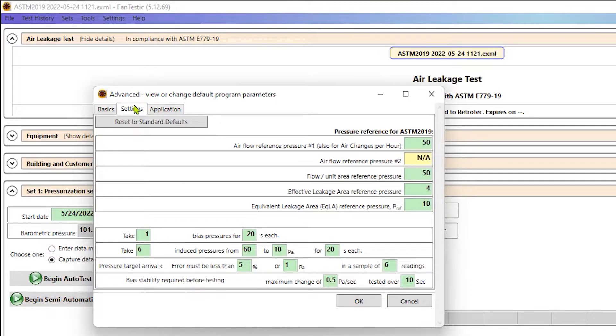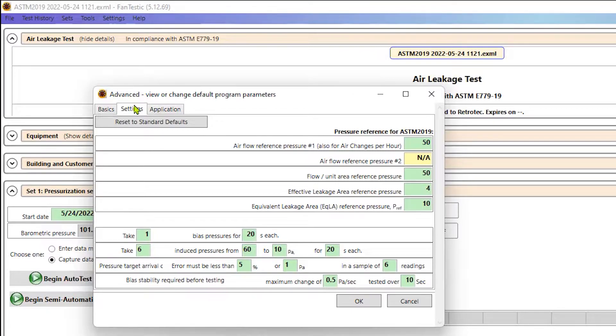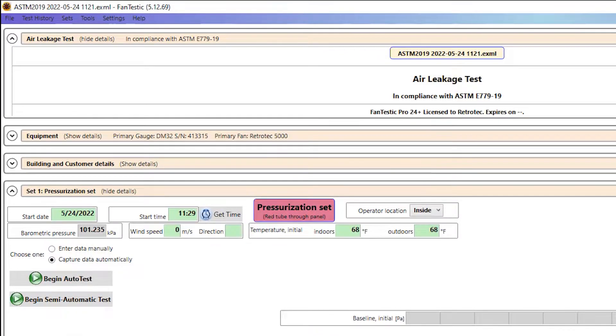And then under the settings tab, this is where we put in our reference pressure. So today, we're going to do a residential test. So our reference pressure is going to be 50 pascals. If we were doing a commercial test, we would change that to 75. And then this is where you put in all your inputs for an auto test too. We'll do that next week. But for now, our reference pressures look good. So I'm happy with this. So I'll select okay.